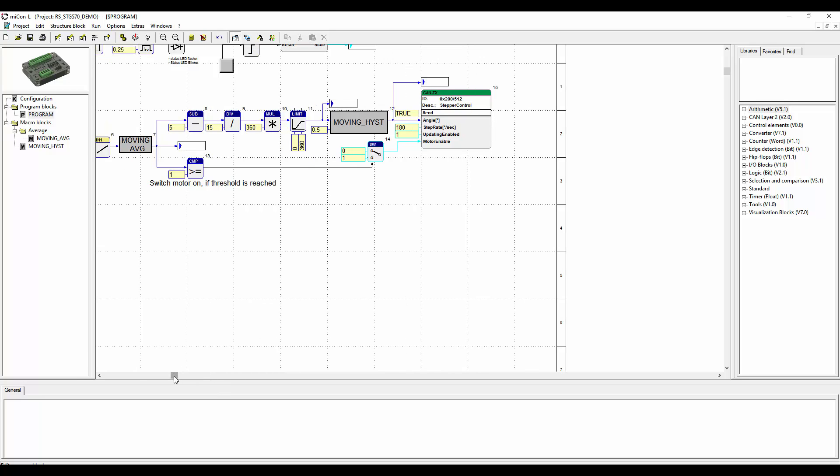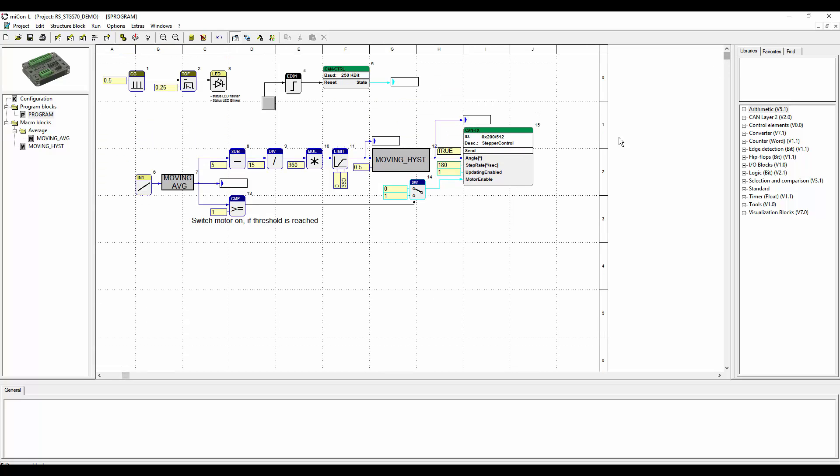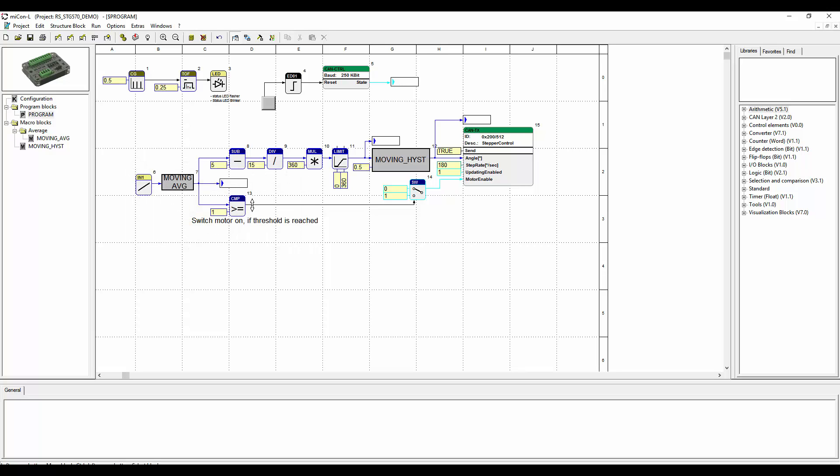The moving hysteresis defines a threshold value and only if this value is overstepped, new data will be released. Now noise does not influence the motor anymore and it runs more quietly. To be able to turn on and turn off the motor, we implemented a comparative function block and the switch. So the motor will turn on if the input is one volt or higher and it will turn off if it's below one volt.